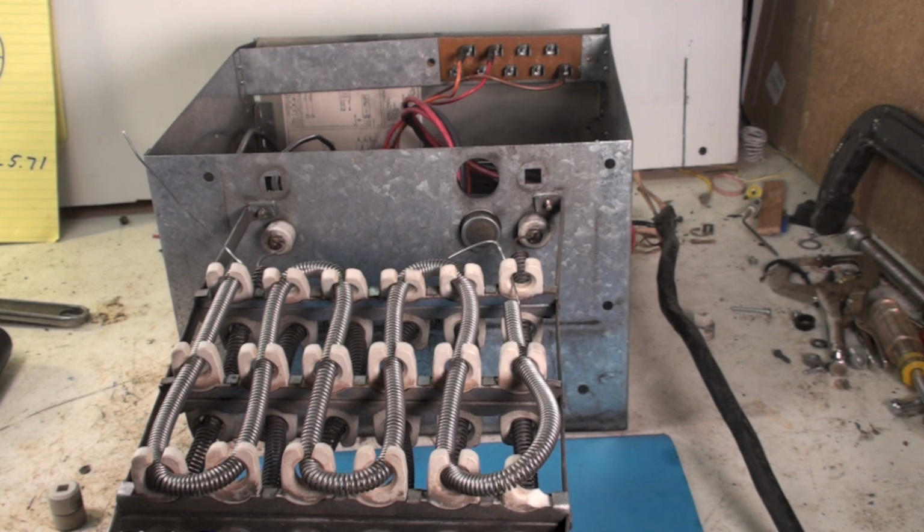Or can you always restring? No. Certainly if the ceramics are broken, you're not going to restring. A couple of manufacturers use a real large diameter wire. I think Trane and Goodman, that I recall, use that. I'm not sure if you can get those or not. I've never had a Trane fail. I've never had one that the element failed in it, so I've never had to replace one.